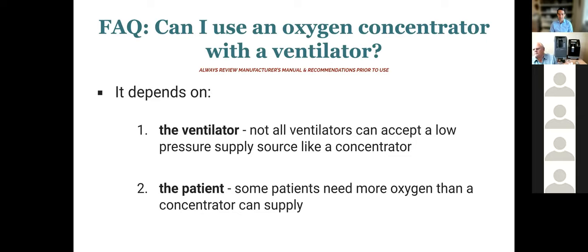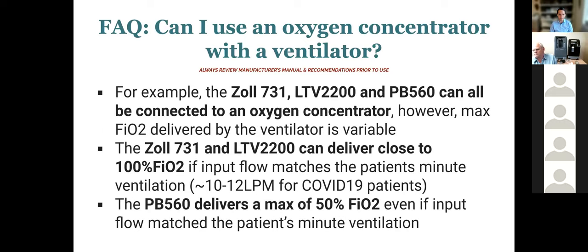Another factor here is the patient. A lot of patients, even if using a ventilator that can accept a low pressure oxygen supply, they may simply need more oxygen than can be provided when using a low pressure supply. For example, the Zoll 731, the LTV2 or LTV2200, and the Medtronic PB560, they can all be connected to an oxygen concentrator, a low pressure oxygen supply. However, the maximum concentration of oxygen that they can then deliver is going to be different. For example, the Zoll 731 and the LTV2, they both can deliver close to 100% oxygen concentration if the flow input matches the patient's minute ventilation.